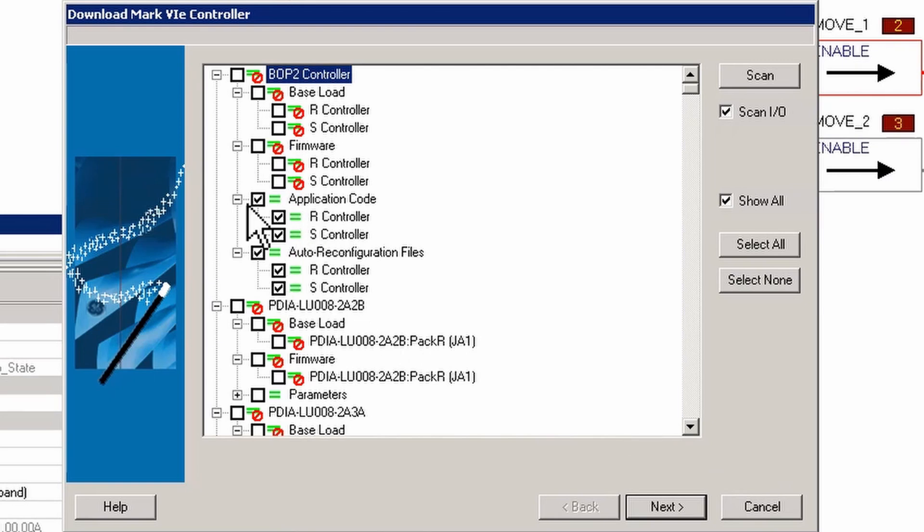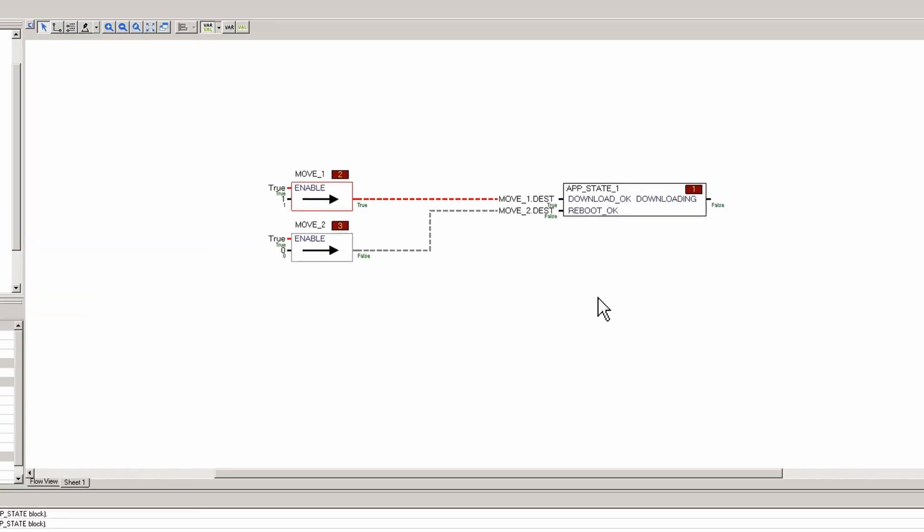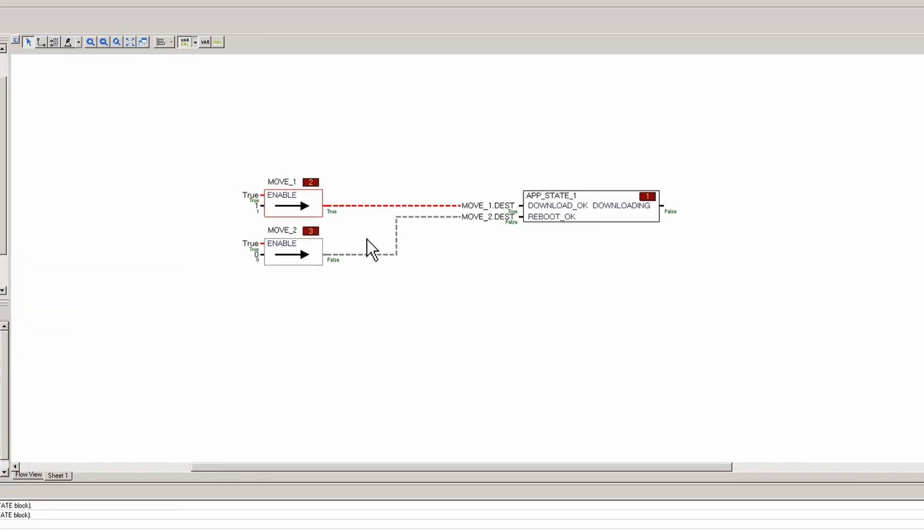And it says hey, you can't do that. Nope, can't do that. It's not going to let you do it. It'll let you do everything but it's going to cancel. And that is how the app state block works. It's a good tool to have so that you don't have accidental reboots on your controller during commissioning or for someone that doesn't understand CMS, which is a common occurrence.